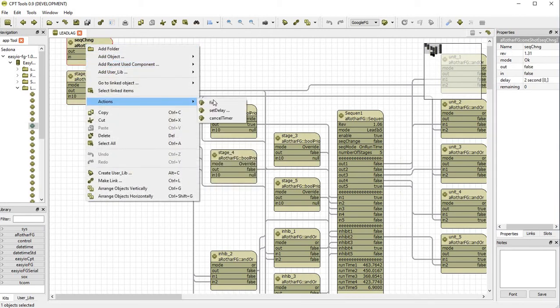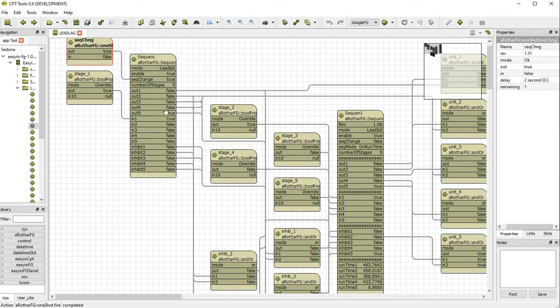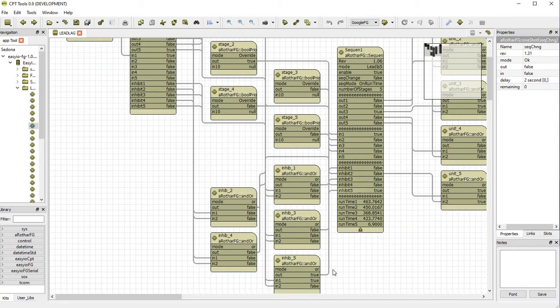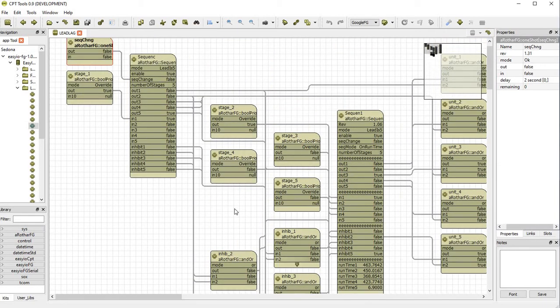Wrong block. So now 5 is the lead, and 3 has started as the following chiller. Now if we went through another sequence change, 5 will stop, 3 will remain running, and 1 will become the lead. The following equipment doesn't have a sequence change unless there is a demand change or a fault change.